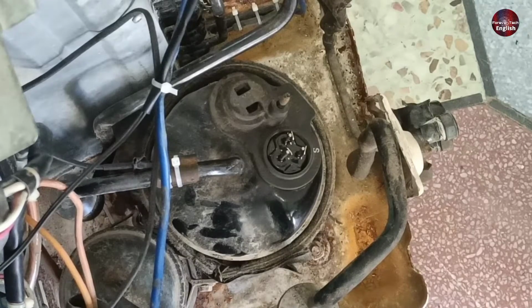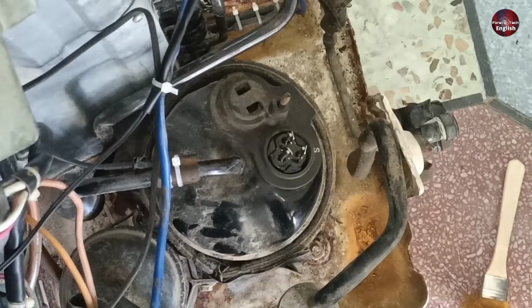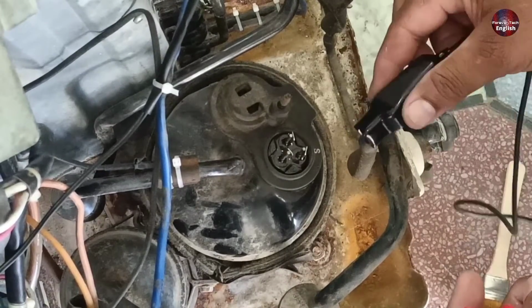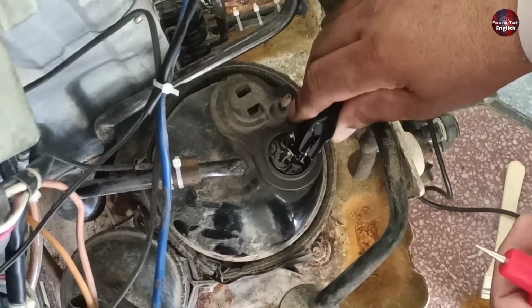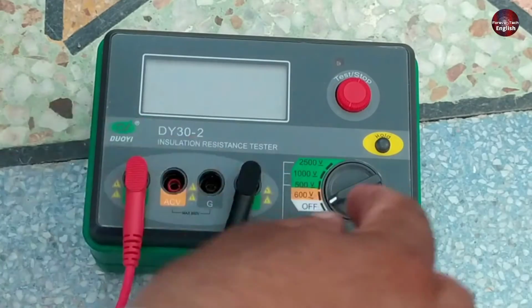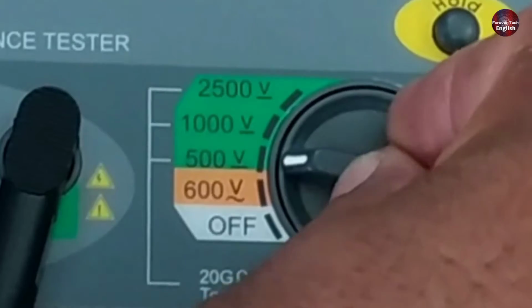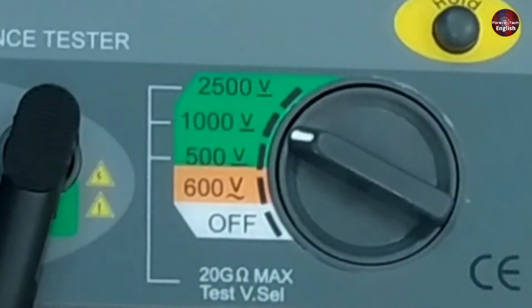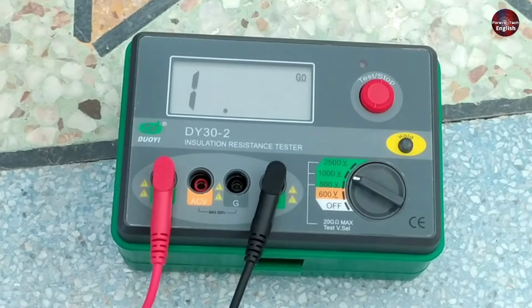Now I am going to test this compressor with the insulation tester. The procedure is the same. I will attach the insulation tester probes to the compressor's terminal. I will test the compressor on 1000 DC volts. Always test the HVAC compressor on the 1000 or 500 volts through any insulation resistance tester.